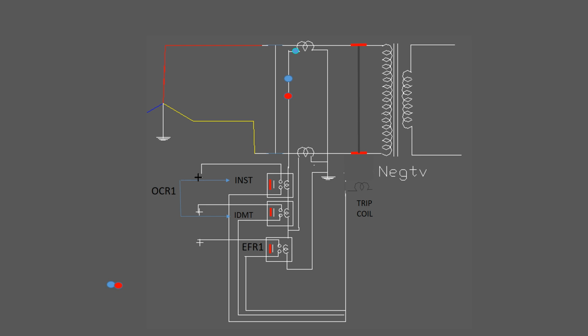And then IDMT, OCR1 IDMT. IDMT is to permit the overloading. Our traction transformer is designed to withstand 200% overload for 5 minutes and 150% overload for 15 minutes. It is permitting that. And then the earth fault relay. The earth fault relay setting current is 10%. So when this 10% current or more enters the earth fault relay, it will trip the circuit breaker.